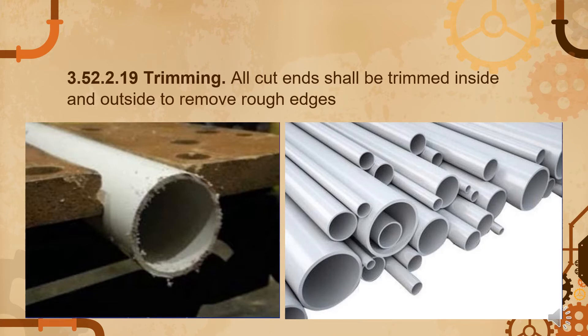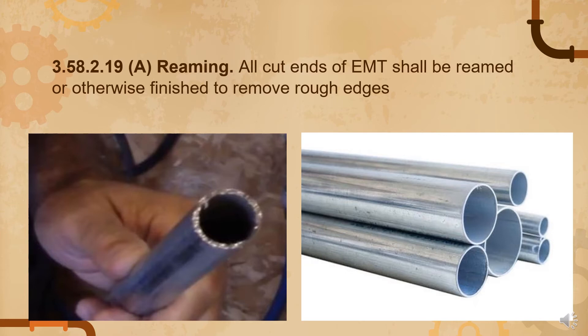Under 3.52.2.19, trimming: all cut ends shall be cleaned inside and outside to remove rough edges. An example is the RTRC, or reinforced thermosetting resin conduit — a fiberglass-like conduit created by tension winding strands of fiberglass over a rotating mandrel. Similarly for reaming, all cut ends of EMT (electrical metallic tubing) must have rough edges removed, which mainly applies to metal conduits like rigid metal conduit and EMT.